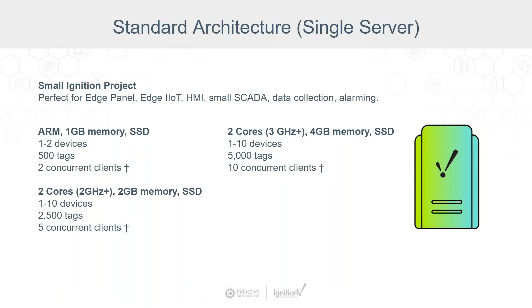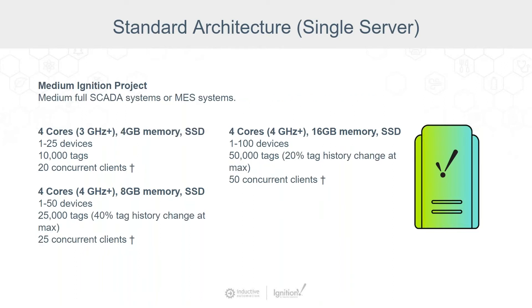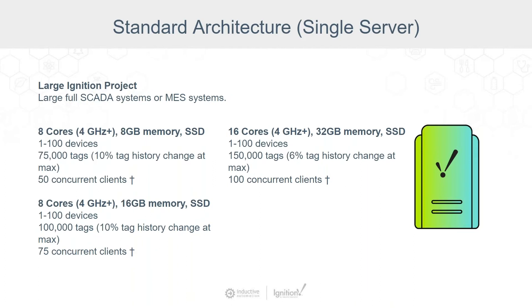These would all be considered small systems. If we go up to a medium-sized Ignition project, these numbers start increasing pretty significantly. Four-core systems with different amounts of memory and processor speeds, going anywhere from one to 25 devices for the smaller ones listed, up to 100 devices for the largest, 10,000 to 50,000 tags, and 25 concurrent clients up to 50.